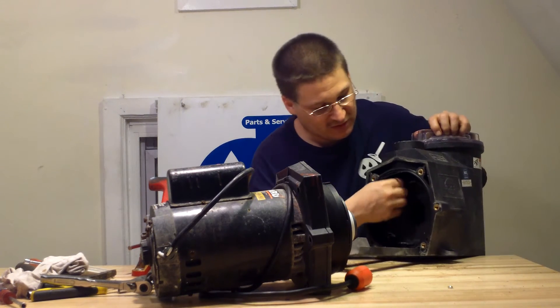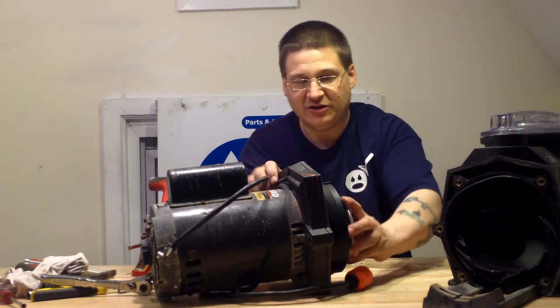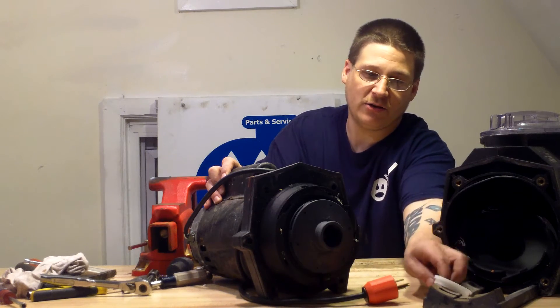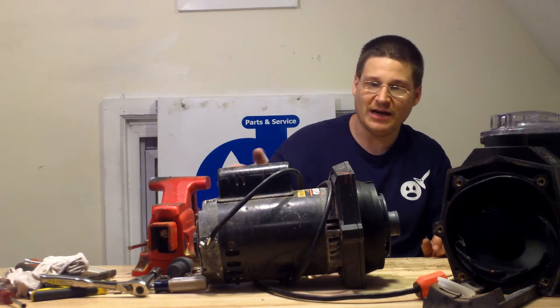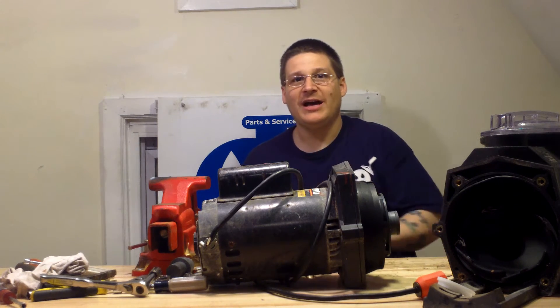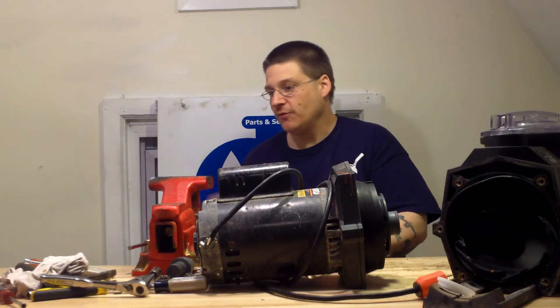You'll see the diffuser is inside here — just like that. Here's the impeller and the diffuser ring, just like that. Take that off. Our next step is going to be to loosen the through bolts and then slide our armature out so we can change the motor bearings. We'll see you in the next video and show you how to remove the motor armature from the pump.